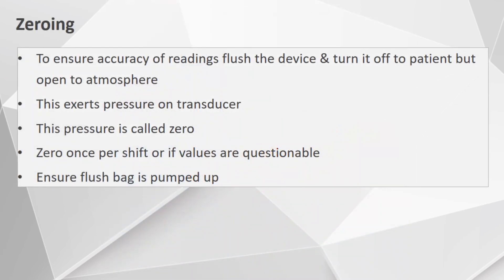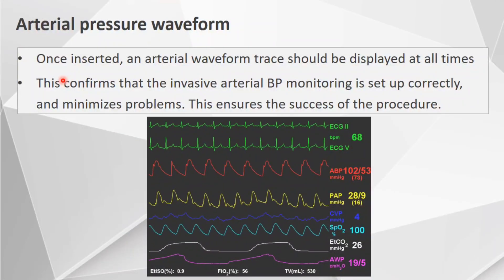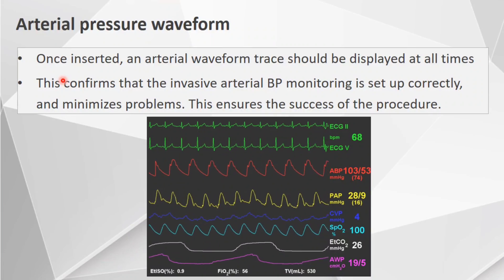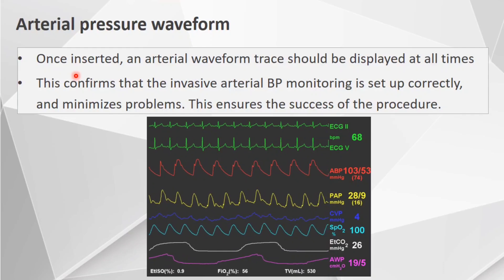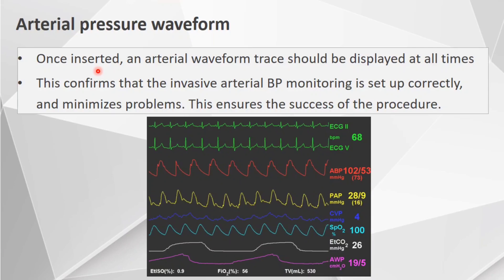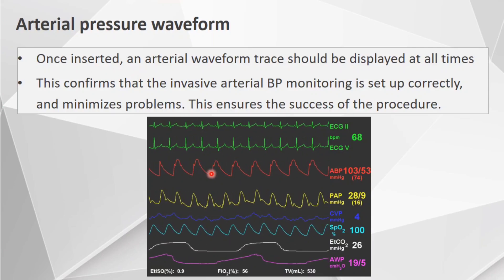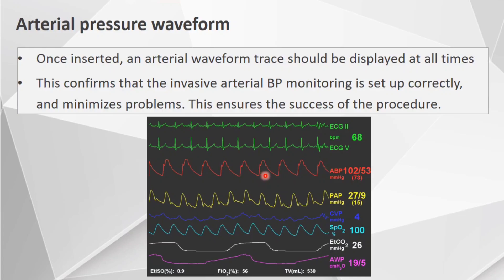The phlebostatic axis is located at the fourth intercostal space in the mid-axillary line, and this is where the transducer zero point should be. Coming to zeroing of the transducer: to ensure accuracy of readings, flush the device and turn it off to the patient but open to the atmosphere. This exerts pressure on the transducer and this pressure is called zero. Zero it once per shift or whenever values are questionable, and ensure the flush bag is pumped up. Once inserted, an arterial waveform trace should be displayed at all times, confirming that invasive arterial BP monitoring is set up correctly.